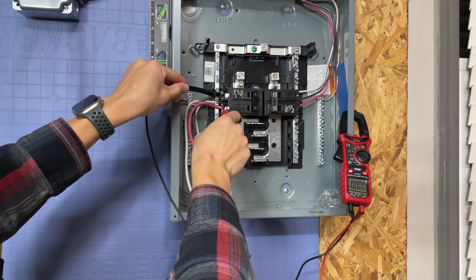So if I take this multimeter, see if you can see it on the screen. If I go from hot to hot, you should get 240 volts, because that's how split phase works - you can see right there, 240 volts. If I go from one leg to ground, you should get 120 volts. And if I go from the other leg to neutral, you also get 120 volts. So 120 volts each leg, but from hot to hot you get 240 - that's where the split phase naming really comes into play.